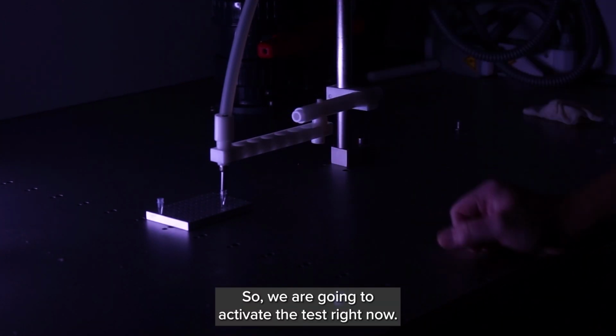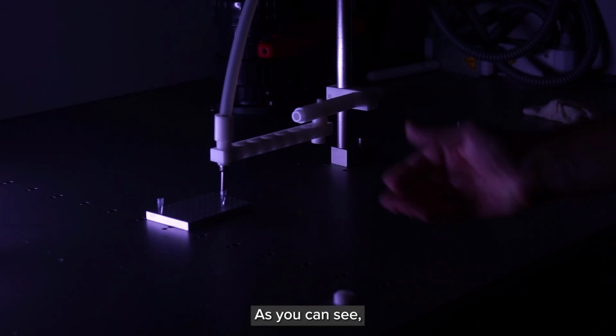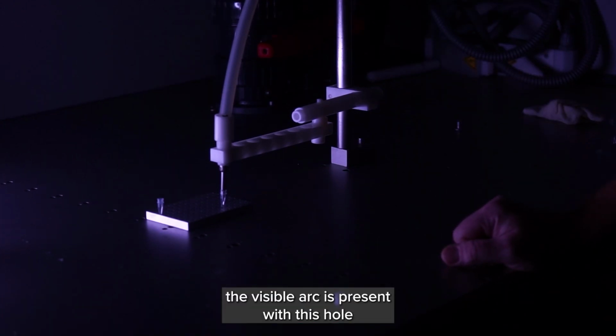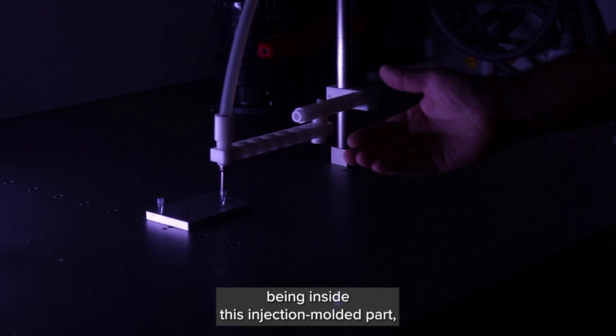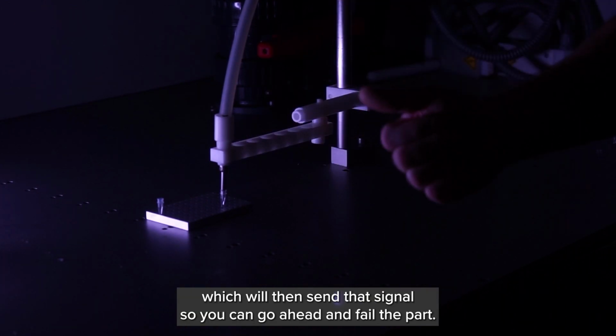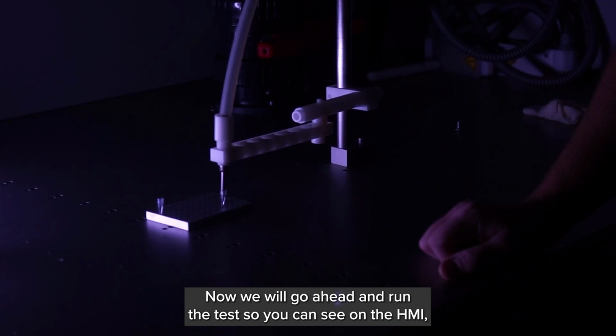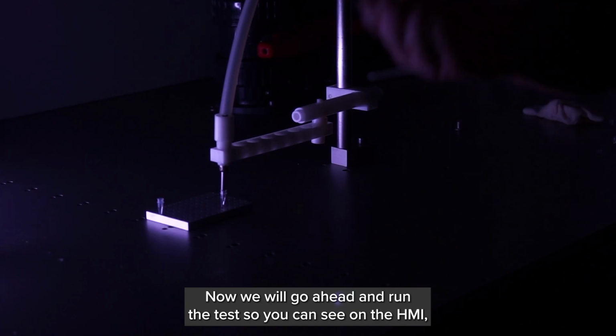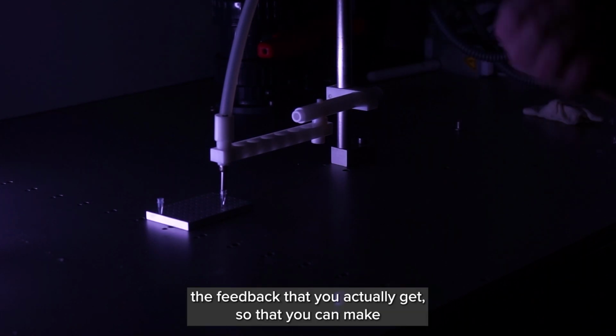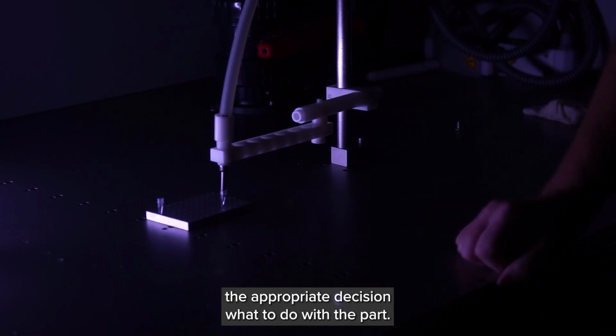So we're going to activate the test right now. As you can see, the visible arc is present with this hole being inside this injection molded part, which would then send that signal so you can go ahead and fail the part. Now we'll go ahead and run the test so you can see on the HMI the feedback that you actually get so that you can make the appropriate decision what to do with the part.